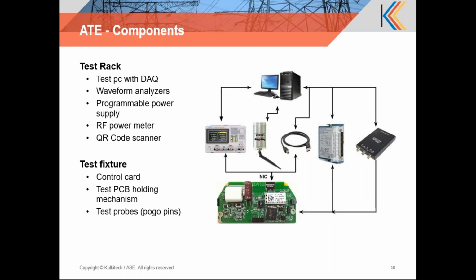The programmable power supply is controlled from the system to ensure that necessary power, necessary voltage has been fed to the system to evaluate different features, and it has to be turned on, turned off, or ramped up as per requirement. RF power meter will be a part in which the RF power or RF functionalities of the device under test is evaluated. If we need to enter the serial number of the product which is being tested, a QR code scanner can also be implemented. And our rack has the functionality that the readings or the entry from the QR code or any other multiple entries can be scanned and fed into the system.